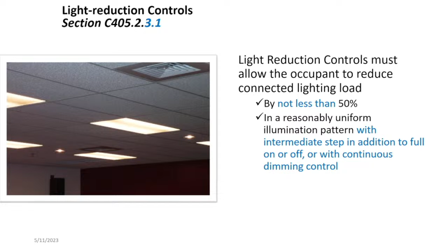And we just talked about not less than 50%, reasonable uniform pattern. Lighting reduction control options, continuous dimming of all luminaires from full down to 20%. Switch all luminaires to reduce output not less than 30%, not more than 70% of full power, and switch alternate.